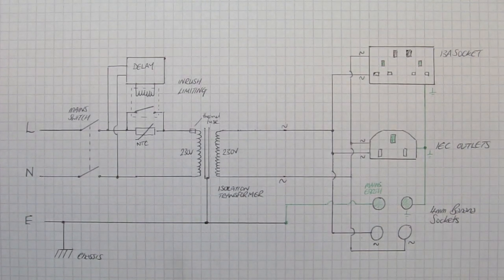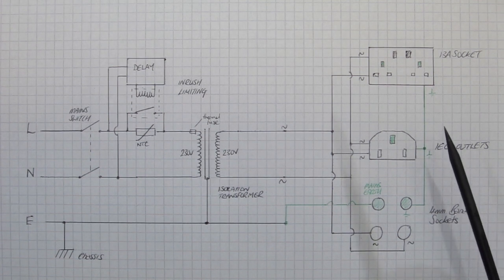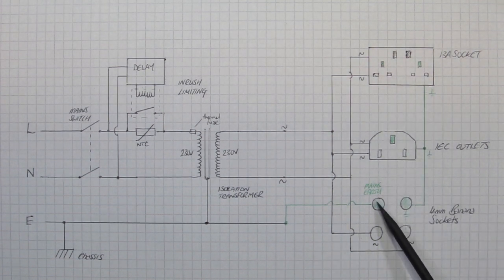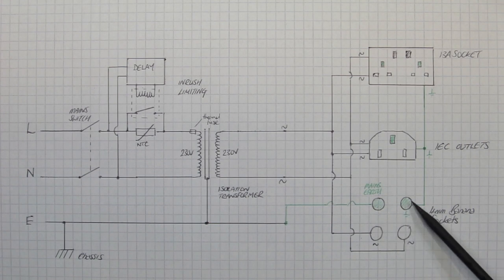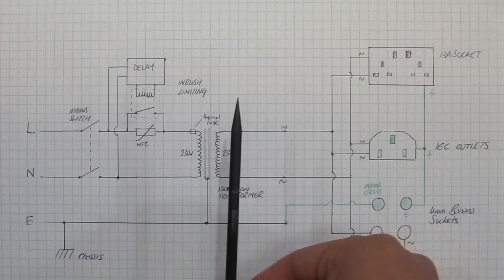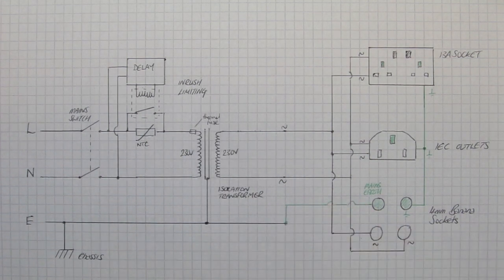And then if I did want mains earth for whatever reason on the outlets, I could just link these two banana plugs together. Or if I wanted to emulate a standard mains connection in the UK where earth is at the same potential as the neutral pin, I could link out the neutral connector with the earth output here, and it would appear like a standard mains connection, but we'd have our full isolation provided by the transformer. So we'll begin wiring up the unit next.